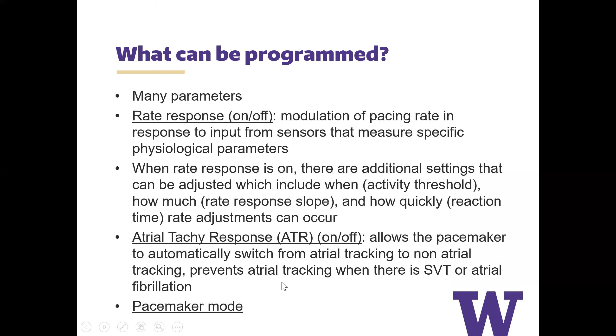Yeah. The first is how does battery life get impacted by the amount of pacing provided? Yes. So if a pacemaker is pacing continuously, theoretically it draws a bit more battery, although these days, because batteries are designed so well, it makes very little impact. It really is when the pacemaker is set at a higher output. So if they're being paced and, for some reason, you can't program to automatic threshold, what that means is they're set at a certain amount of volts delivered over a certain amount of time. When that number is high and that's chronic, it will drain the battery.